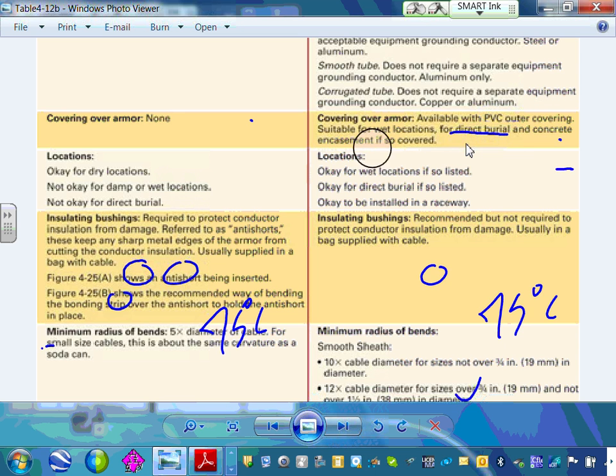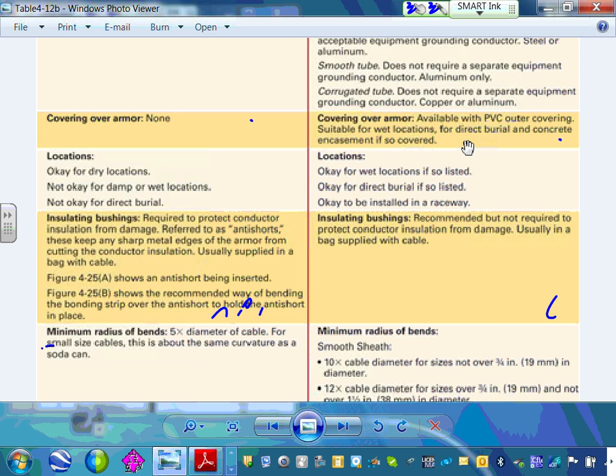So where can you use this cable? This is another very important feature, guys, of that wiring method. Look at that. Okay for dry, no problem. Not okay for damp or wet location. Not okay for direct burial. Wet location, no problem, but there is a difference between wet location and direct burial.